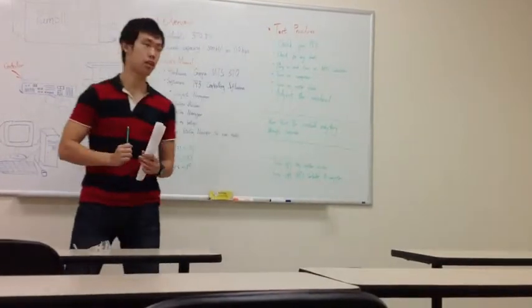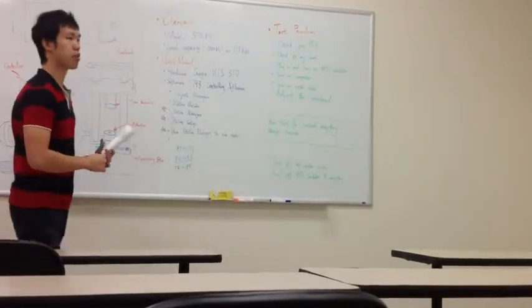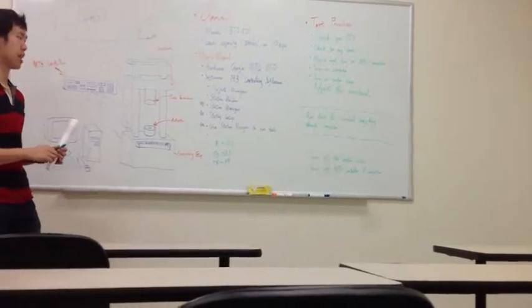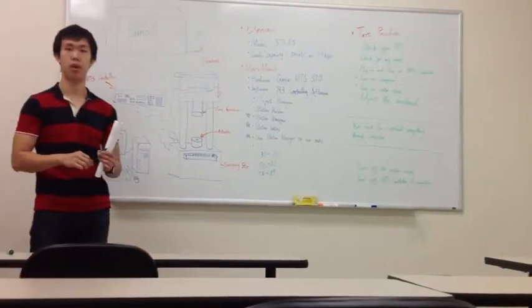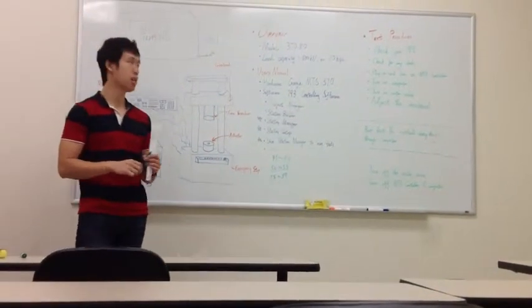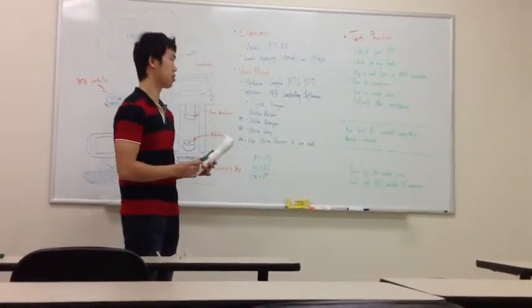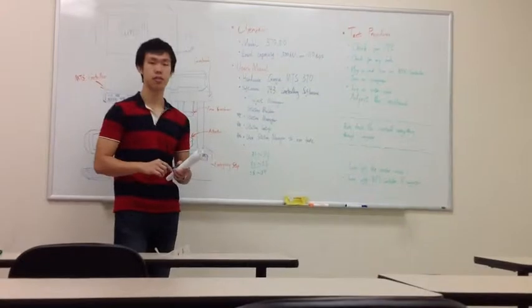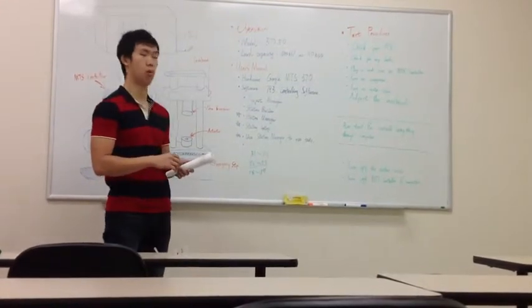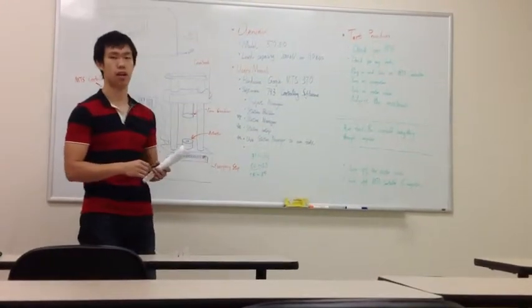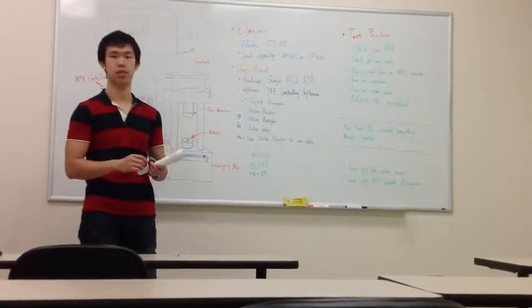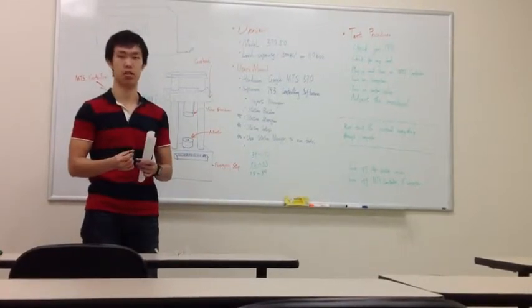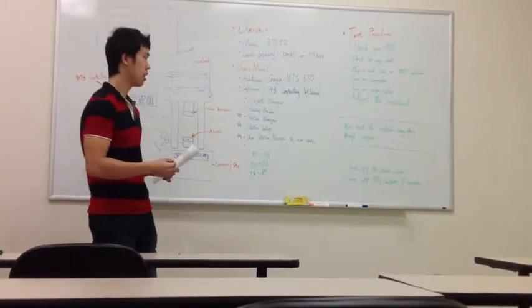You will need to turn on the MTS controller first to allow the MTS machine to warm up a little bit. Then after that, you turn on your computer and turn on the water valve. The purpose of water valve is to make sure the MTS pump doesn't overheat.